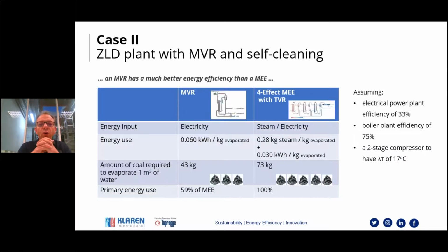To zoom in a bit on how big this effect is on the energy consumption of an MVR compared to an MEE, this is also worked out in a white paper, which is enclosed with this webinar as a handout, so you can read more about it there. But the core is, as I already explained, that you use all the latent heat and recover it in the condenser section of the heat exchanger. So if you then really do the mathematics, you need to take some assumptions. For example, in this case we have taken coal as the primary source. If you want to convert coal to electricity and to steam, you need to take some assumptions about efficiency, which you can see on the right.